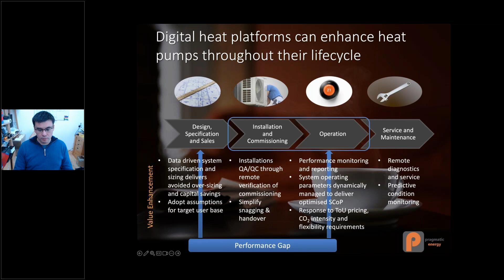So if we drill into that a little bit, what do we mean by a performance gap? Well, at design there was an assumption about the weather, and it's quite often a little bit warmer than in reality. Warmer weather means lower demand anyway, and because heat pumps prefer it slightly warmer outside, the heat pump itself will have a higher COP, coefficient of performance. So there'll be less demand to meet, and it'll need less energy to meet that smaller demand.